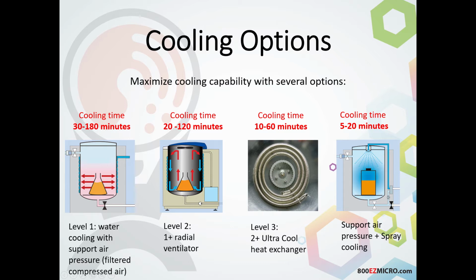The level 2 would be a radial ventilator, so we can place a fan inside of the instrument that will fan that environment inside. So instead of just radiation of the cooling water to the bottles, we can fan the system inside as well, so we get 50% more efficiency and use a lot less water. We can also, in that radial ventilator, put an additional heat exchanger inside of there. That additional heat exchanger will increase our efficiency even further, again using less water. So the radial ventilator and the ultra-cool are actually fairly inexpensive options that will pay for themselves very quickly, just in use of tap water alone.